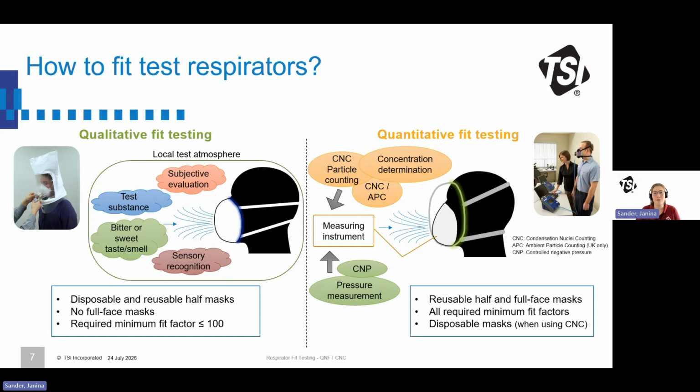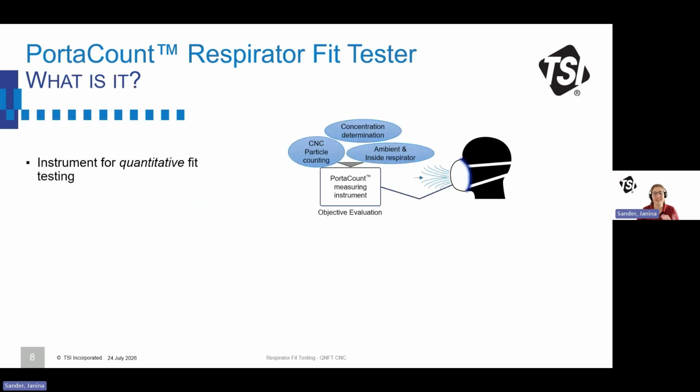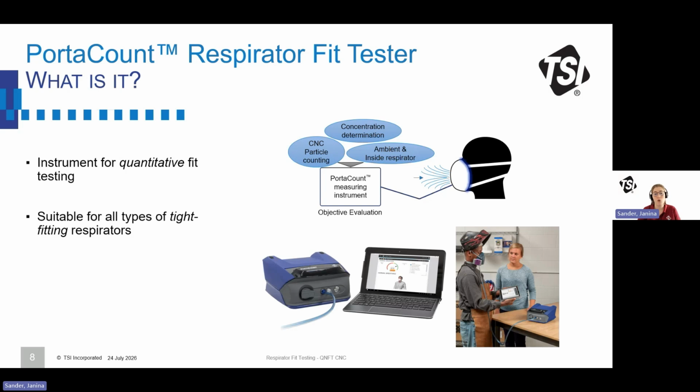There are, of course, other instruments on the market as well, but as I'm from TSI, I can only talk about our instrument in detail. Just as a general introduction, the Portacount is specifically designed for quantitative fit testing, for an objective evaluation of a respirator's fit by counting particles and determining the concentration in the ambient air and inside the respirator. As this is using the CNC technology, the instrument is suitable for all types of tight-fitting respirators, from FFP masks to a full-face respirator.